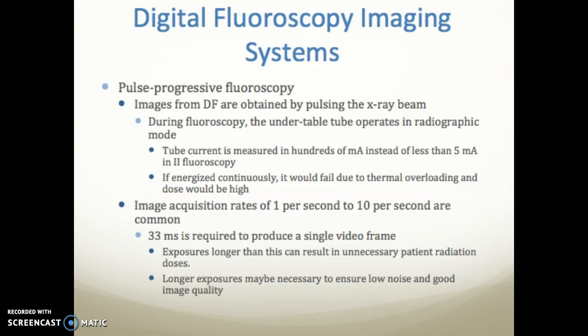In a digital fluoroscopic imaging system, you have pulse progressive fluoroscopy. Images are obtained by pulsing the x-ray beam. During fluoroscopy, the under-table tube operates in radiographic mode, with tube current measured in hundreds of mA instead of less than 5 mA in a conventional II. If energized continuously, the tube would fail due to heat overloading. Image acquisition rates of 1 to 10 per second are common. 33 milliseconds is required to produce a single video frame; exposures longer than this result in unnecessary patient dose, though longer exposures may be needed for low noise in pediatric cardiac imaging.